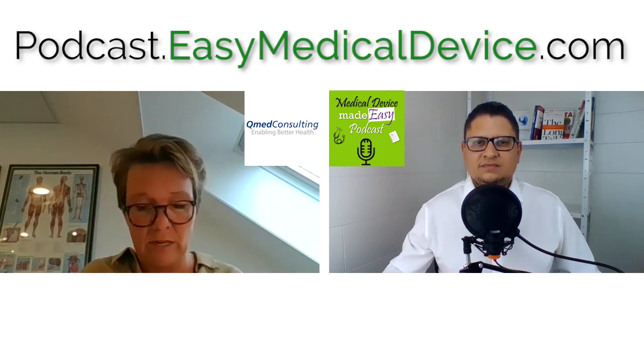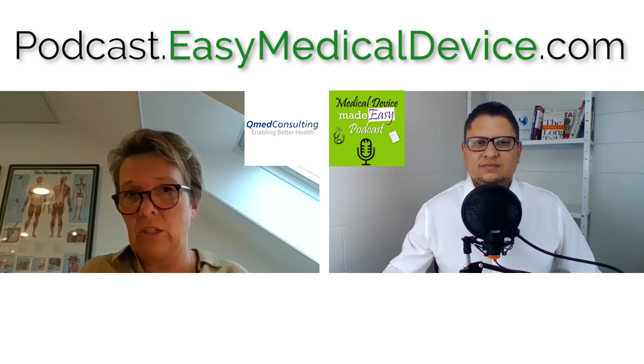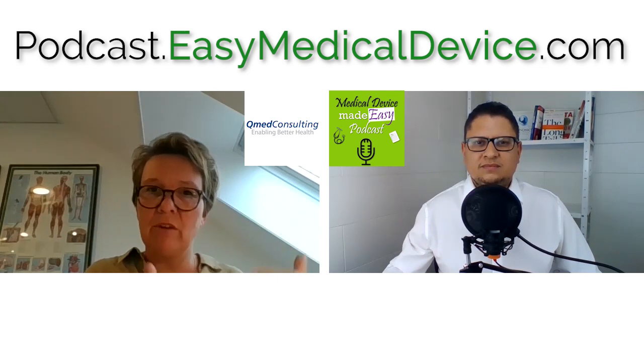And Qmed has actually been so kind, clear is kind, to go out and say what we mean by sufficient amount and quality, and specified it very clearly. Basically, amount means that you should have a statistical rationale behind your product: the right number of patients with a sufficient amount of products, all the target groups covered, your claims covered, and safety and performance, so your essential requirements are covered. It goes line by line through what you need to do.